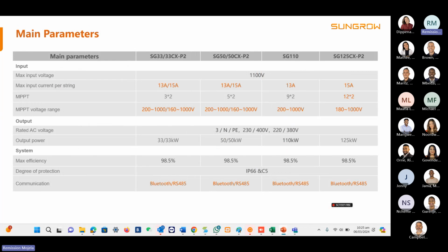And then the difference, I've just highlighted the difference of all the devices, is that the 33 CX and the 33 CX P2, the 33 can only handle up to 13 amps per MPPT string. So in total, one MPPT on the CX takes up to 26 amps. After that, it will cap the current. And then the P2 will take up to 30. All of the P2s, just like that, will take up to 30, but the CX versions will only take up to 26.